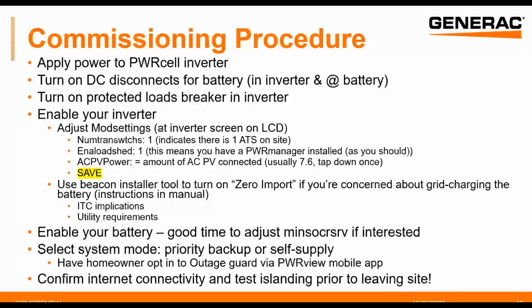So then before you click out, make sure you save all of the settings on the inverter at the bottom of the screen. We've definitely had calls into tech support from folks who thought there was an equipment issue, but the reality is they just hadn't saved their settings, which is a pretty easy one to fix. Then if you need to turn on zero import, which will prevent the battery from grid charging, which may be required by your utility. We've seen this from some utilities.